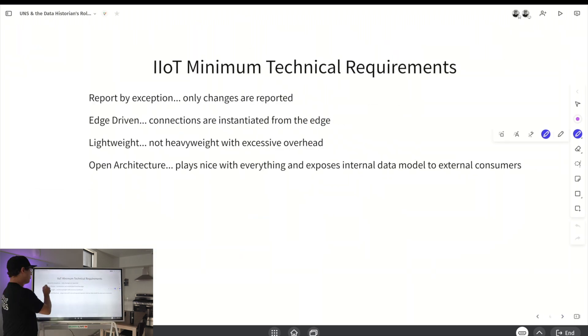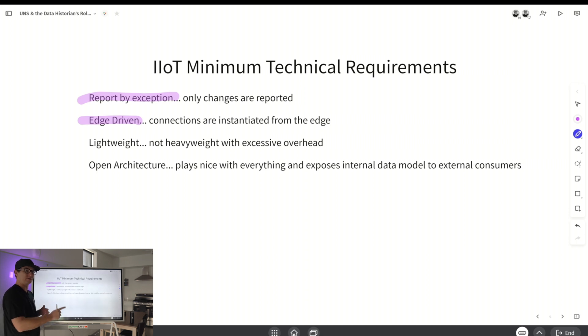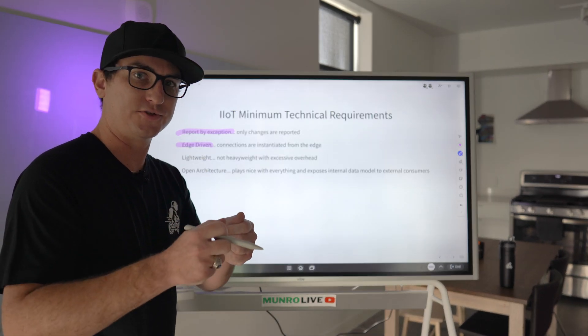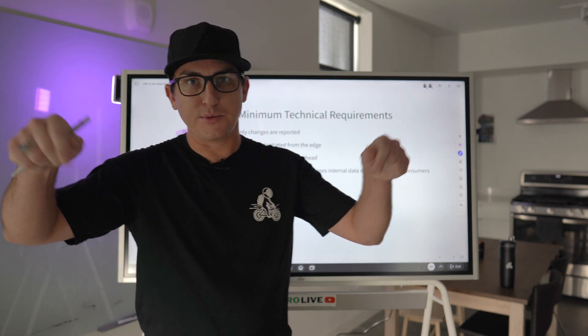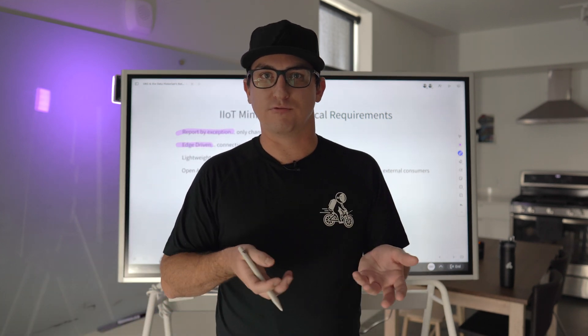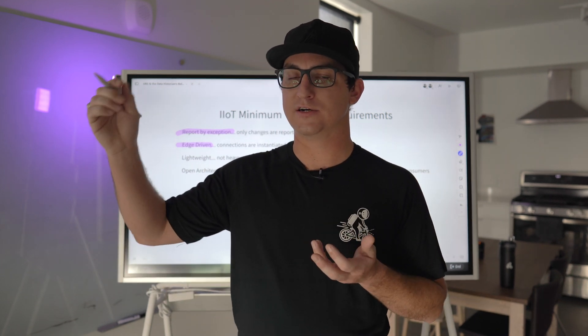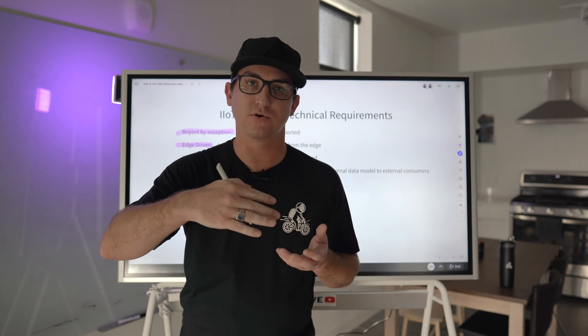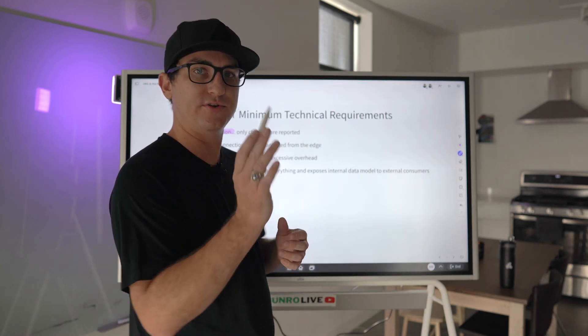The IIoT minimum technical requirements are: report by exception — only changes in the data are reported, as opposed to poll response. Edge-driven — connections are instantiated from the edge. This is important for scalability: you're not going to the server to configure your new historian tag like you would with, say, a Wonderware historian. That's server-centric, as opposed to edge-driven.